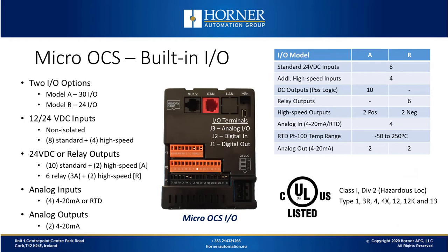Now let's talk about the Micro OCS with its built-in IO. With the Micro OCS, you've got two options. Model A is based around DC IO including DC outputs. Model R is based around DC inputs and relay outputs. There are 30 IO points with Model A and 24 with Model R. The inputs are 12 or 24-volt compatible and non-isolated. Eight of the inputs are standard inputs, four of which are high-speed, which could be used with high-speed counting type applications. Model A uses 24-volt DC outputs — 10 standard and 2 high-speed. Model R uses six relays rated for up to 3 amps, then two solid state outputs, plus two additional high-speed outputs that are not relay.